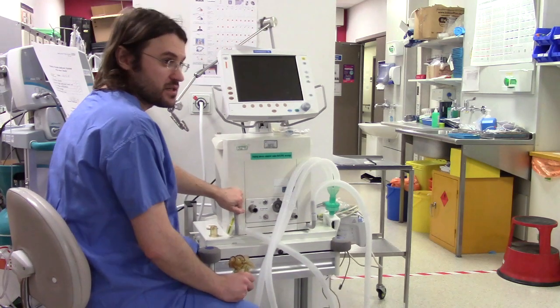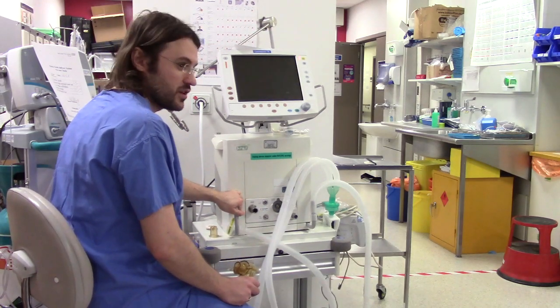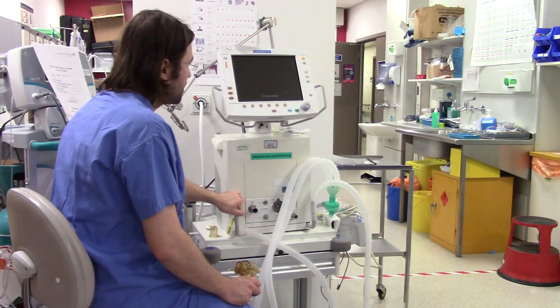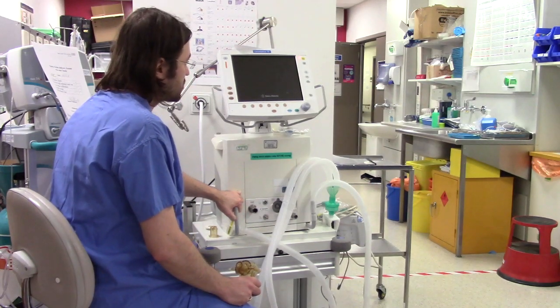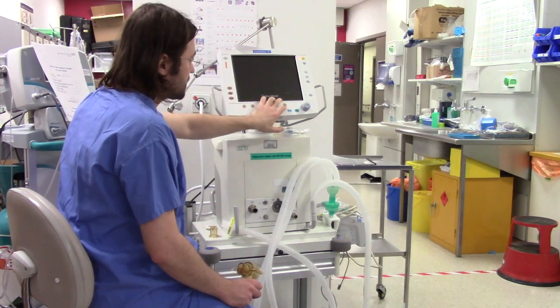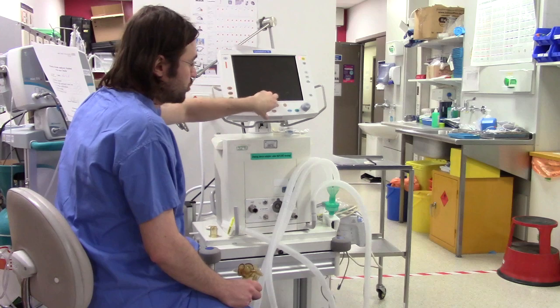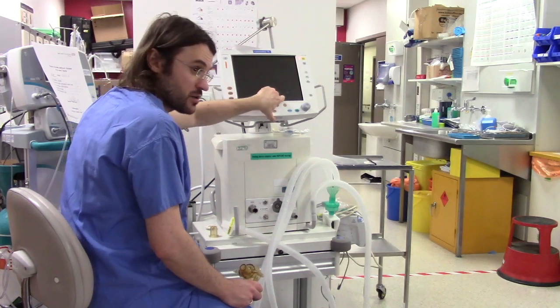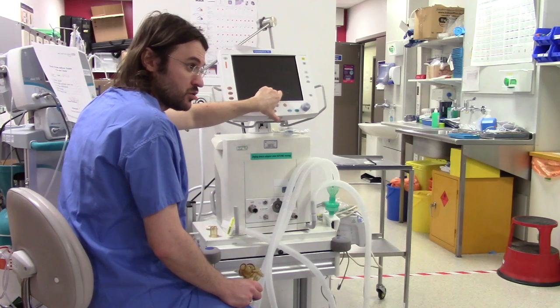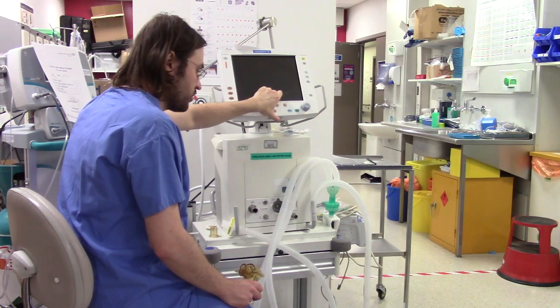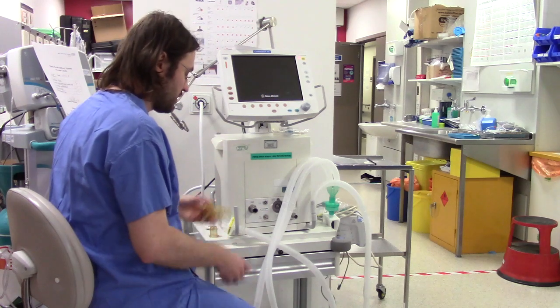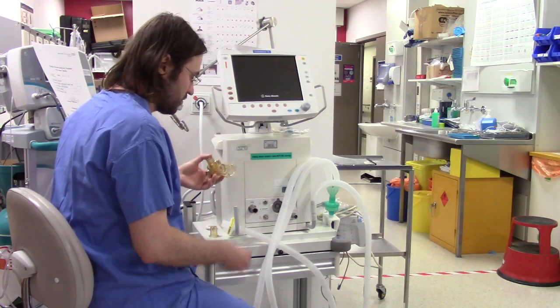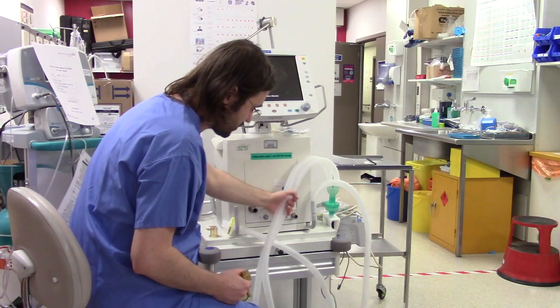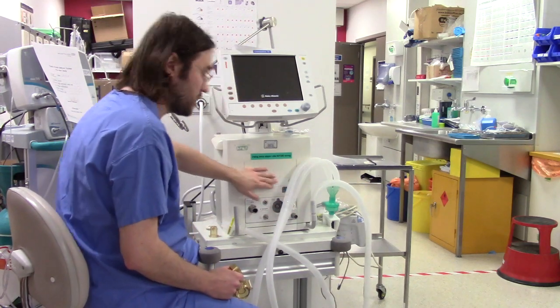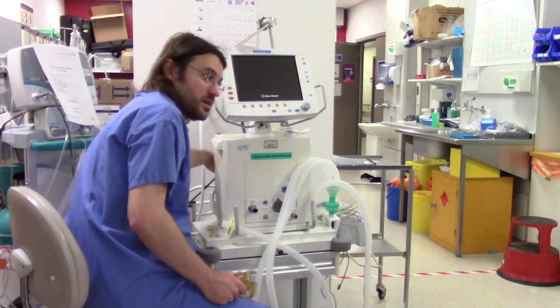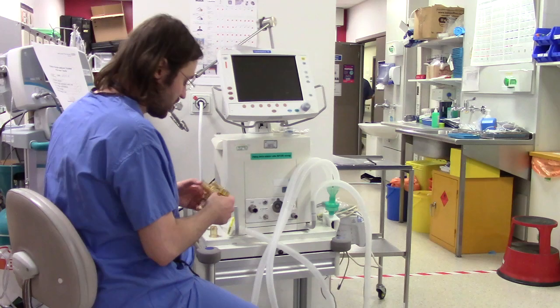This is the sound it makes at the beginning, so don't be scared of it, yeah. It takes approximately 30 seconds to load up and do a quick self-test, and after that it will prompt us to do a pre-use check. So basically you do a check before connecting it to the patient, yeah. This way you can check the integrity of this block, which I'll talk about a bit later, integrity of the circuit, if the valves inside are working, if the supply of oxygen and air is good enough, and so on, yeah.